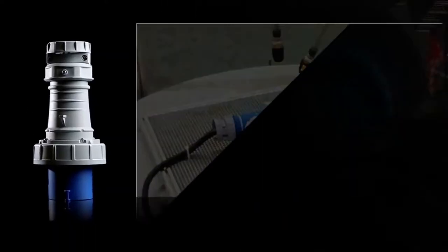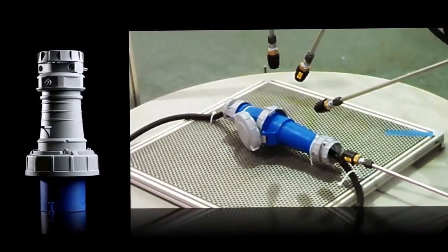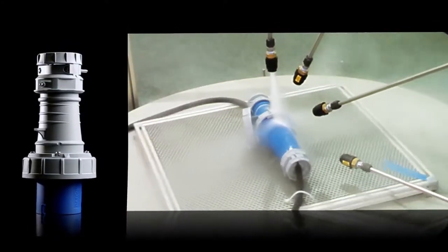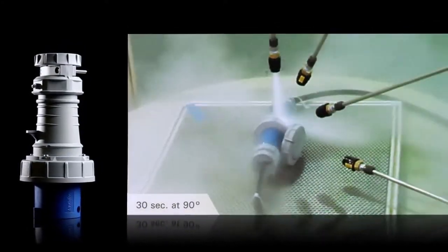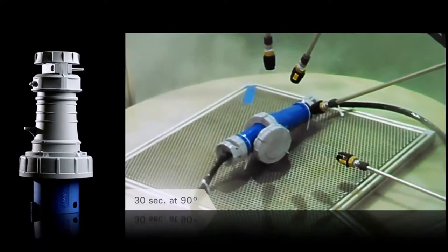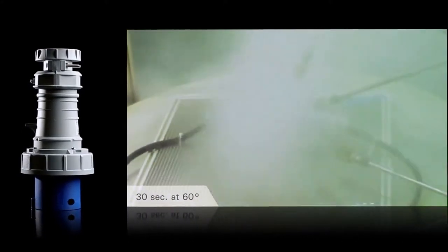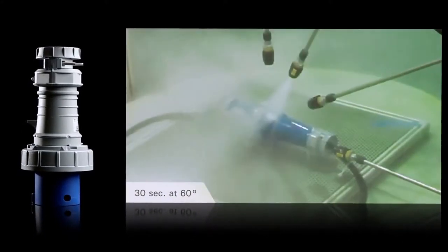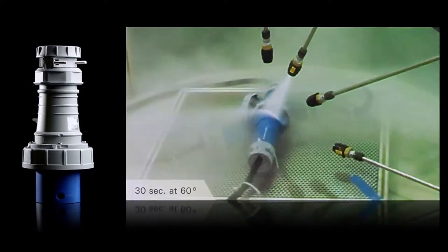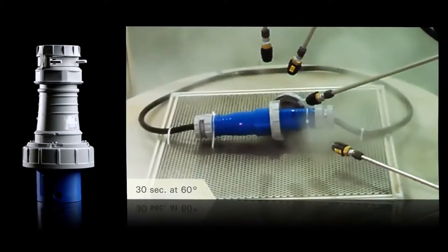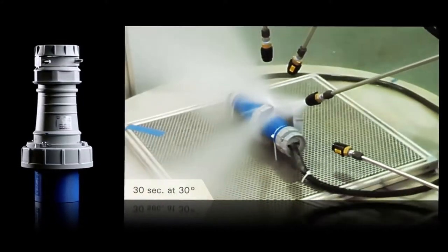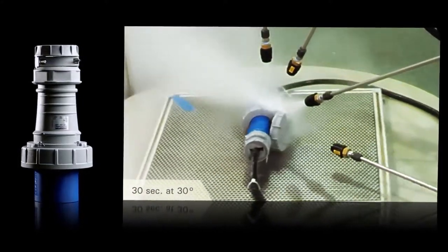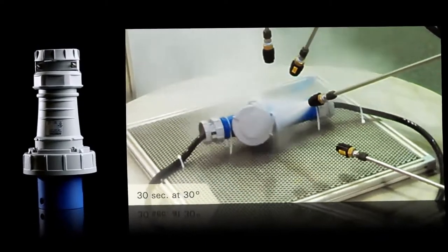The test method requires the device to be subjected to 1500 PSI water spray at 176 degrees Fahrenheit from a distance of 4 to 6 inches. This test is one of the most severe methods of ensuring equipment can handle a harsh washdown environment.